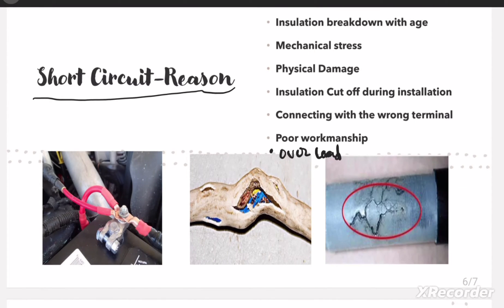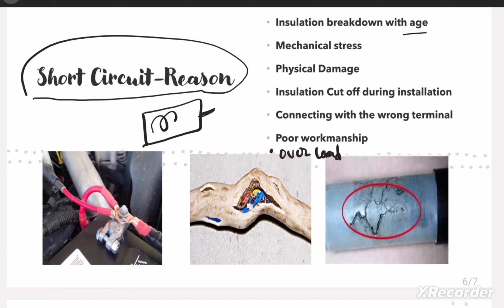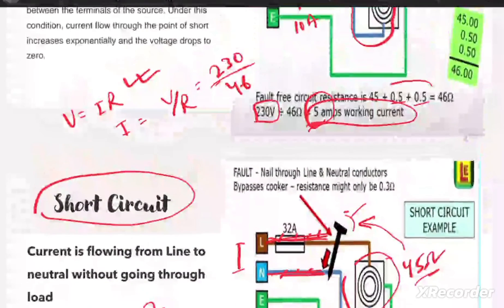Now let us understand some reasons for short circuit. First, insulation breakdown with age — when a motor is very old, the winding insulation degrades over time and becomes ineffective, creating a short circuit. Second, mechanical stress — due to mechanical stress, a cable can detach from its terminal and touch another terminal, leading to short circuit. Third, physical damage — as demonstrated, a nail puncturing the line and neutral wire creates a short circuit.